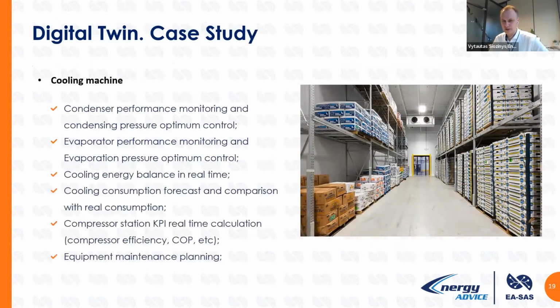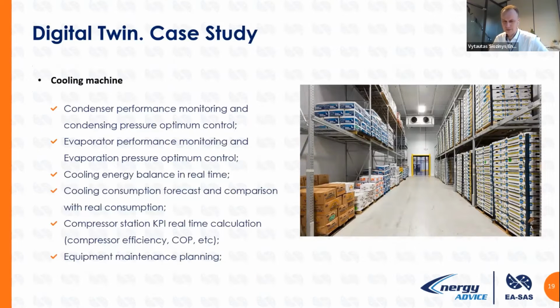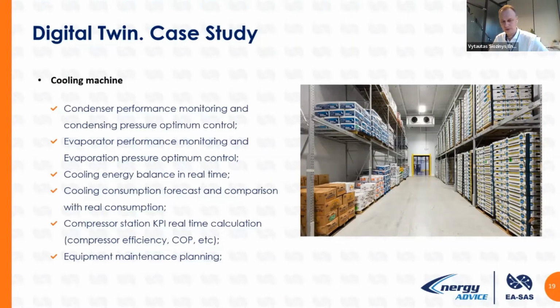Another case is a cooling machine. In general, when we observe a cooling machine, we should take into consideration condenser performance and condensing pressure optimum control, or pressure and temperature, which are related parameters. Also evaporator performance, evaporation pressure and optimum control, and cooling energy balance in real time. If we have a cooling agent like water, we can have a flow meter and understand the cooling energy flowing. But if we have ammonia or freon, we usually don't have a mass flow meter.